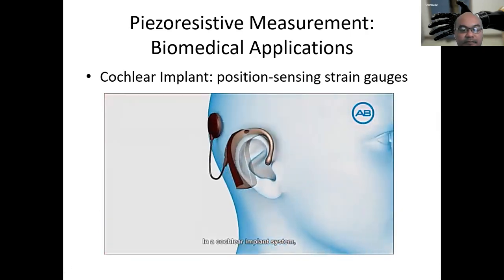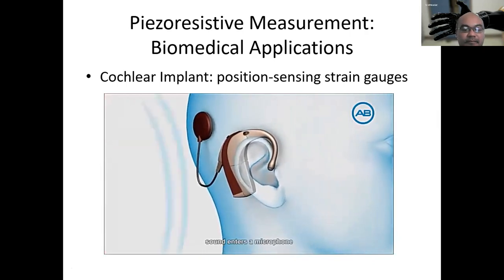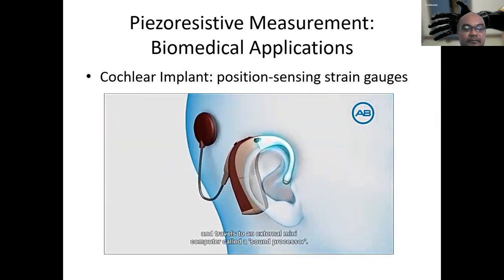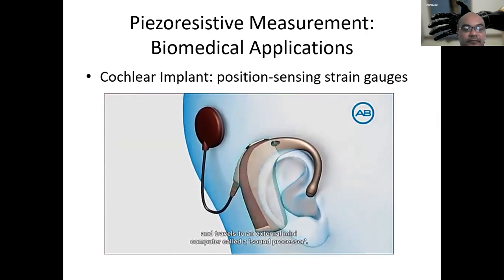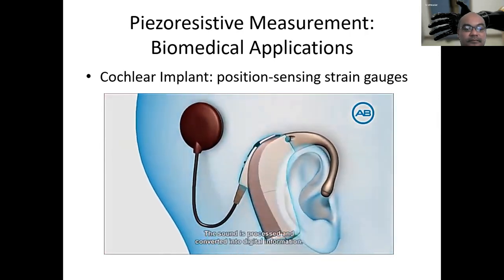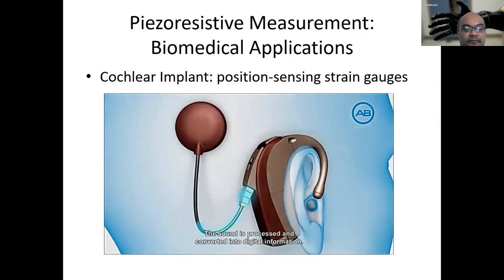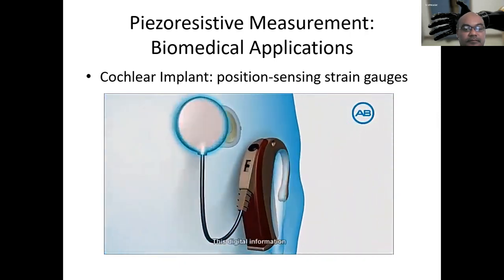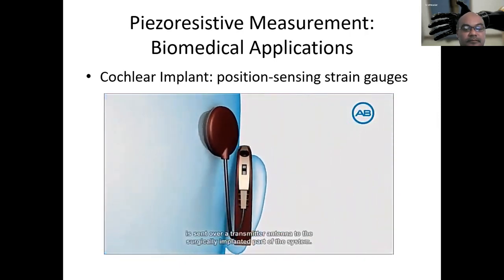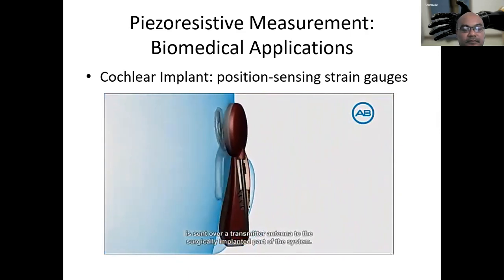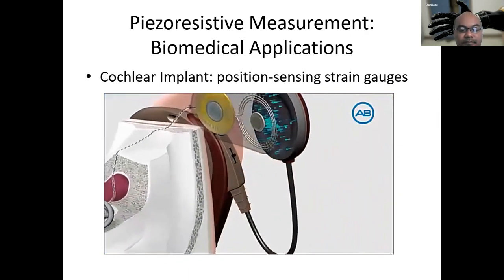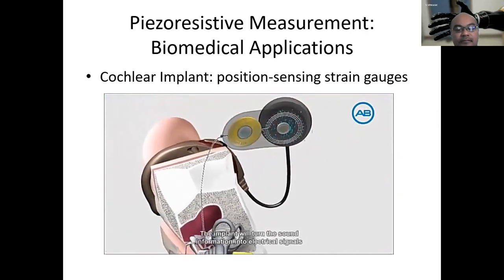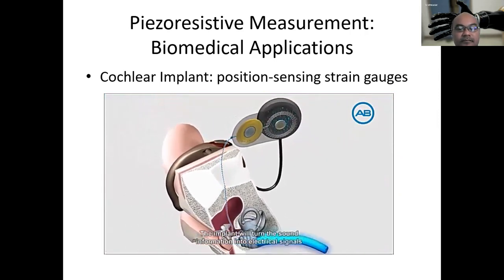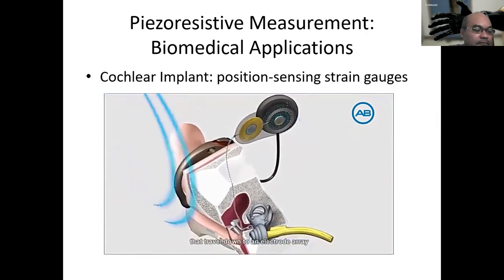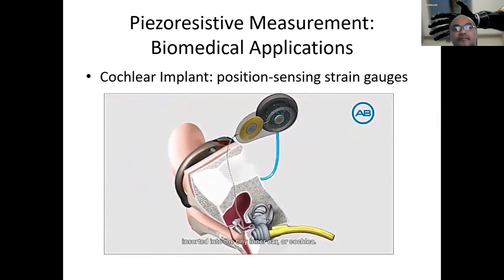In a cochlear implant system, sound enters a microphone and travels to an external mini-computer called a sound processor. The sound is processed and converted into digital information, which is sent over a transmitter antenna to the surgically implanted part of the system. The implant turns the sound information into electrical signals that travel down to an electrode array inserted into the tiny inner ear, or cochlea.